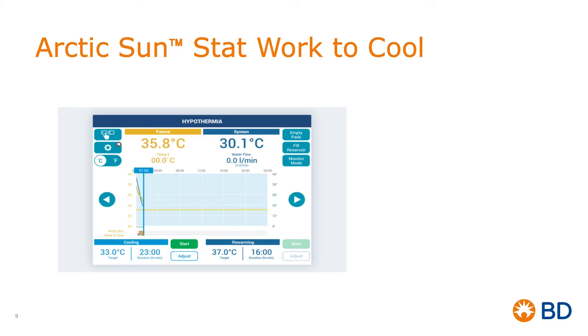The solid yellow line is your actual patient temperature. The solid blue line is the actual water temperature. The device checks your patient's temperature every second and adjusts the water temperature every two minutes, eliminating the need for manual adjustments.